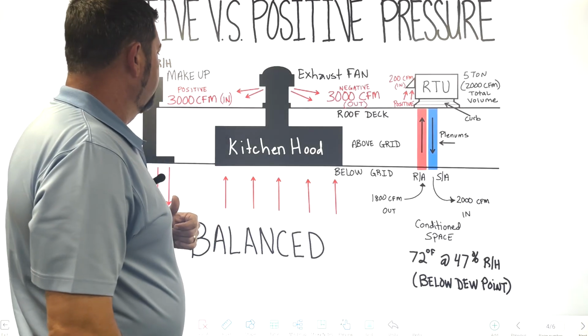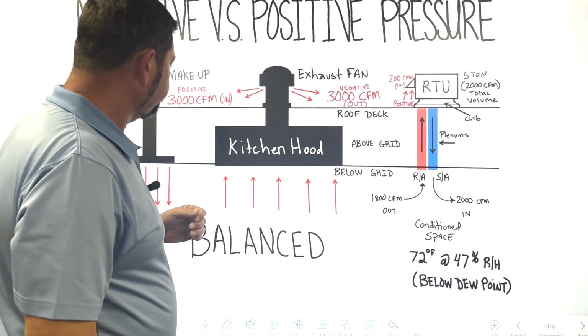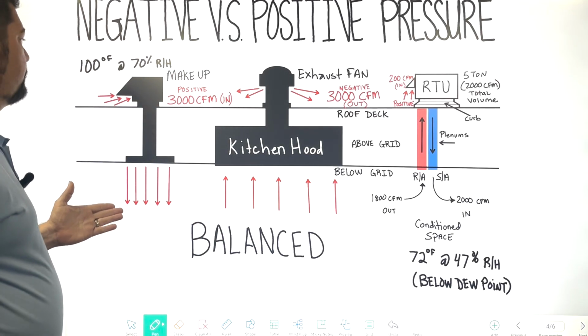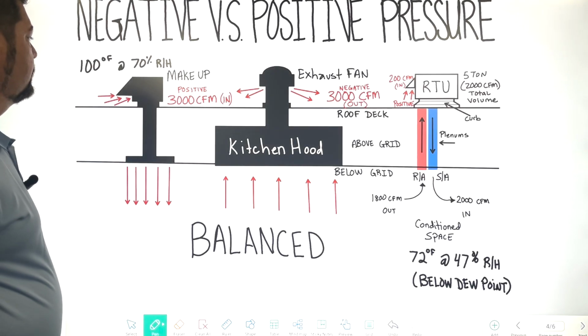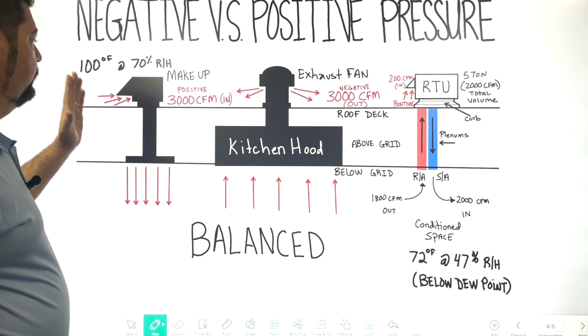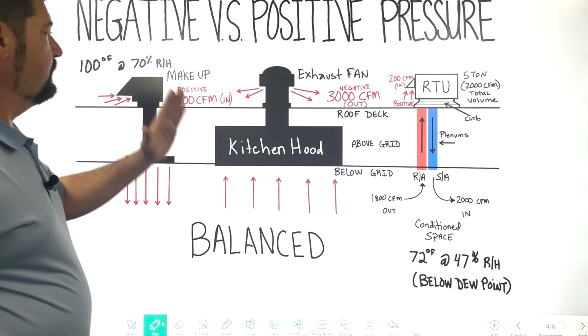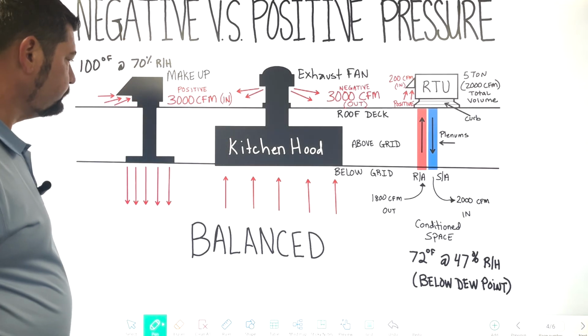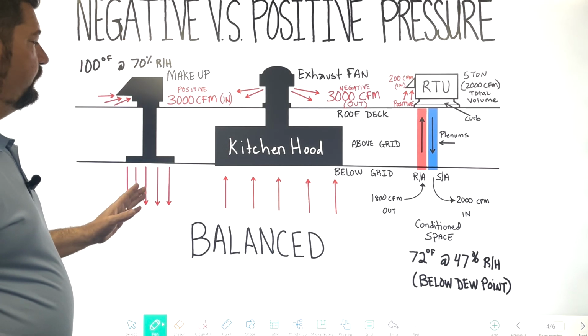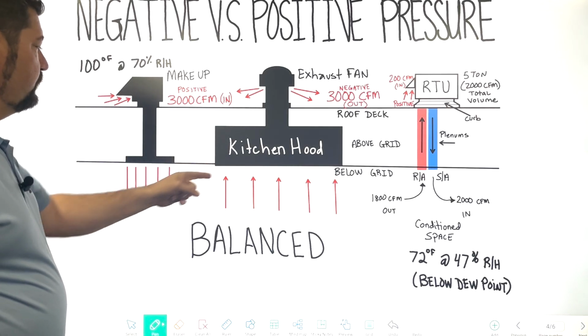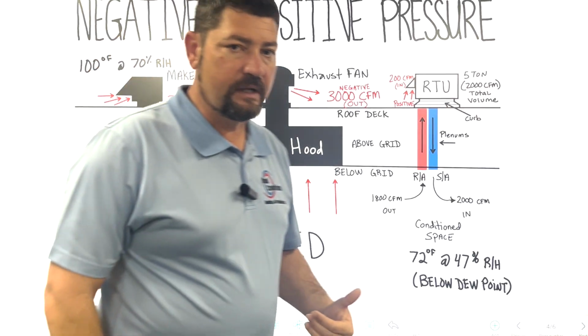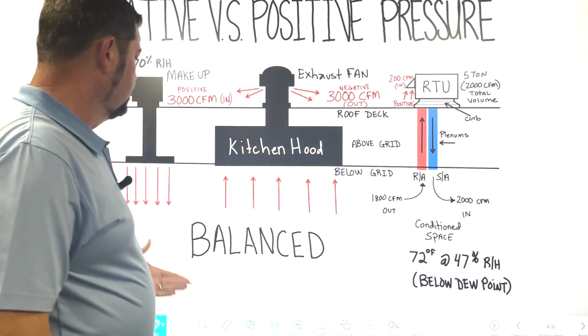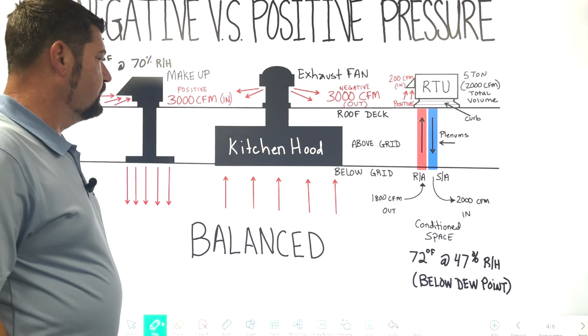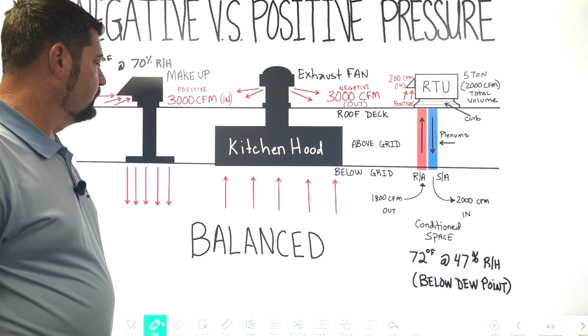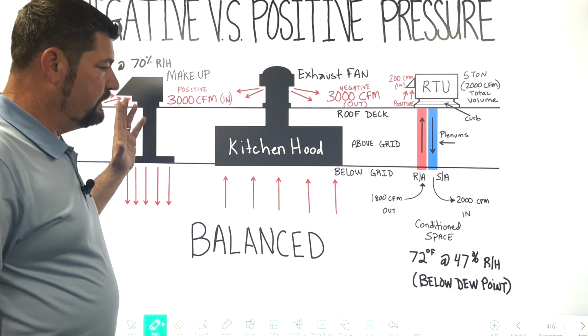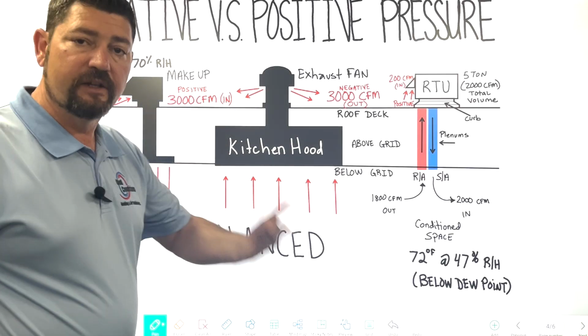Another thing to take note of is, let's just say my positive air is working and my exhaust fan is down, and maybe the problem is the wiring that was done between these two, so they don't both come on at the same time. I've seen that in older buildings where things really have just been kind of put together due to budgets and whatnot.